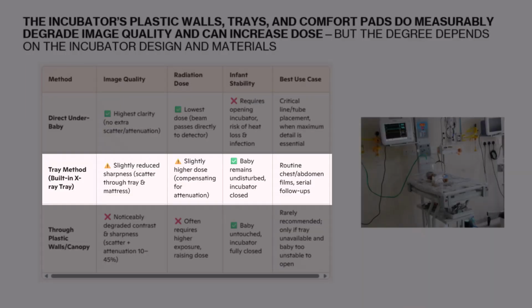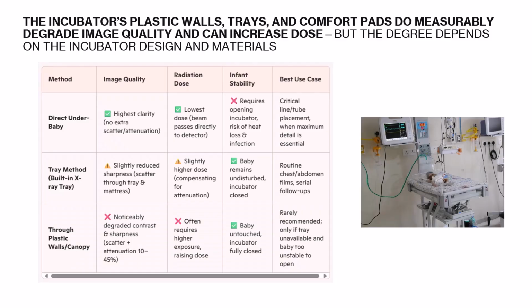The other method, the tray method, where there's a built-in tray in the incubator, we're going to use that for our receptor and then actually X-ray through the incubator itself, which of course degrades the image and causes attenuation of up to about 10 to 45%. The tray method is acceptable for follow-ups and stable babies where small losses in sharpness are tolerable. Direct under-baby placement is preferred when maximum clarity is desired.